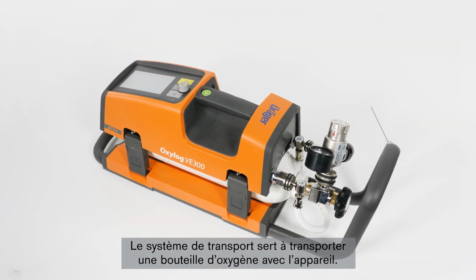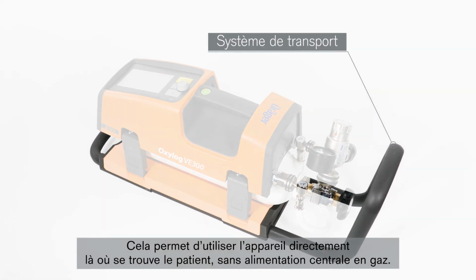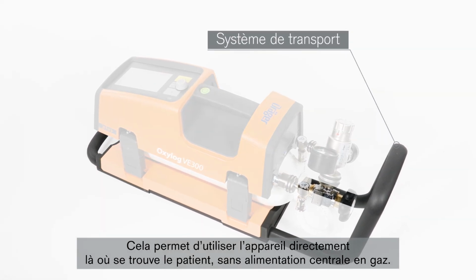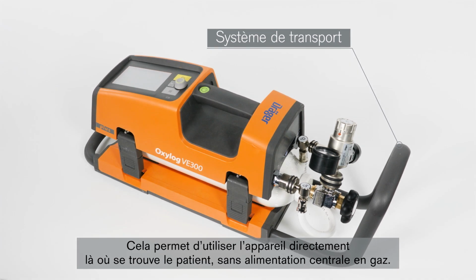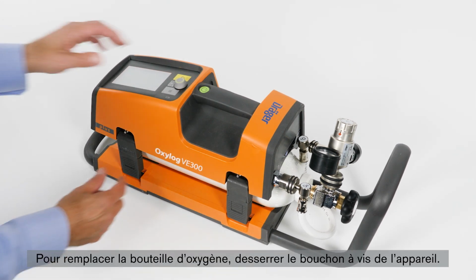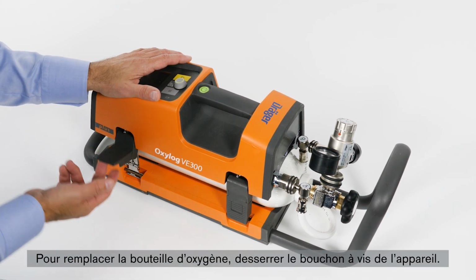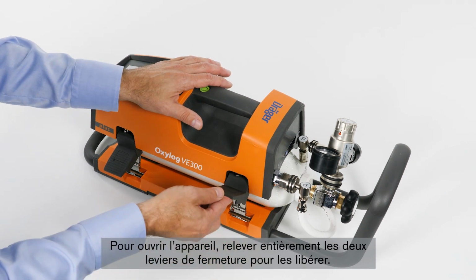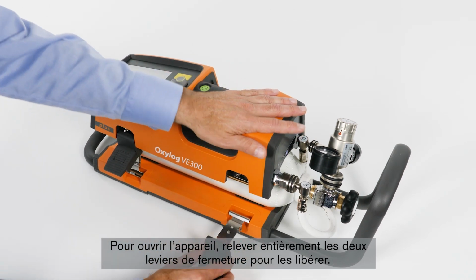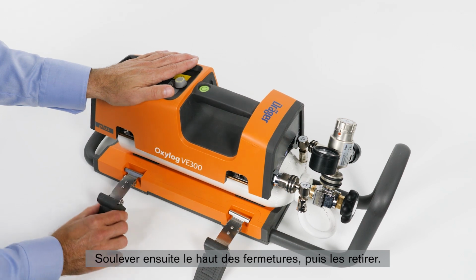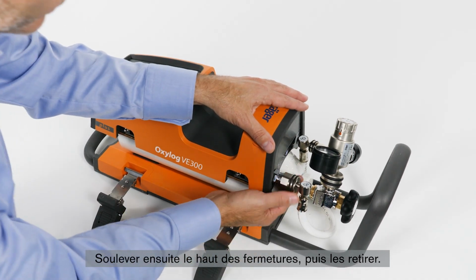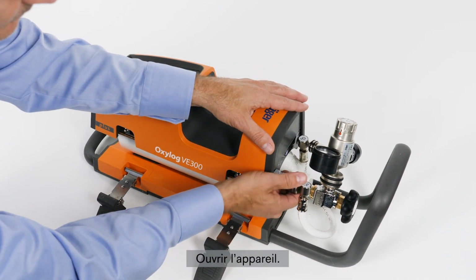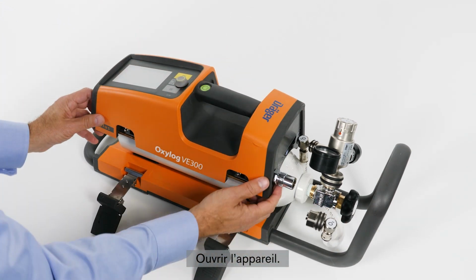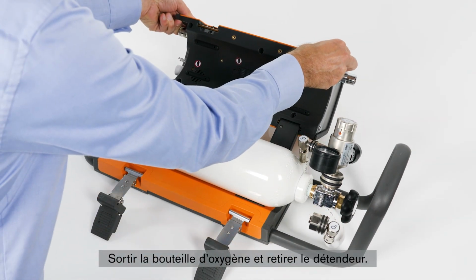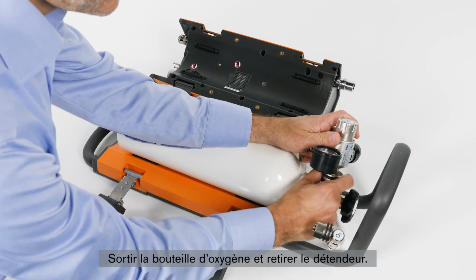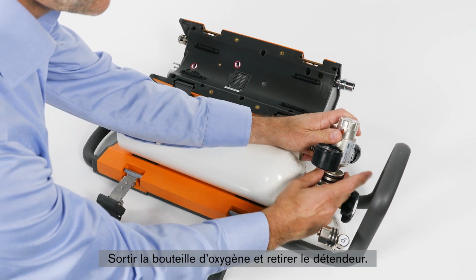The carrying system can be used to transport an oxygen cylinder together with the device. This enables the device to be operated directly at the patient's location, independent of a central gas supply. To change the oxygen cylinder, loosen the screw cap on the device. Open the closure of the device by lifting both handles to the top and release them. Now lift the upper part of the closures upwards and pull them off. Open the device. Take out the oxygen cylinder and remove the pressure reducer.